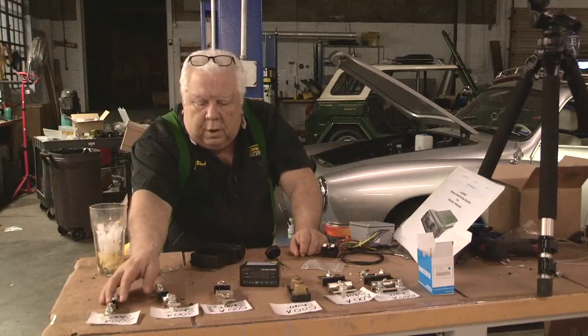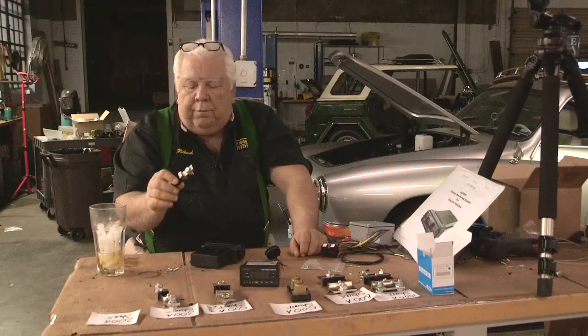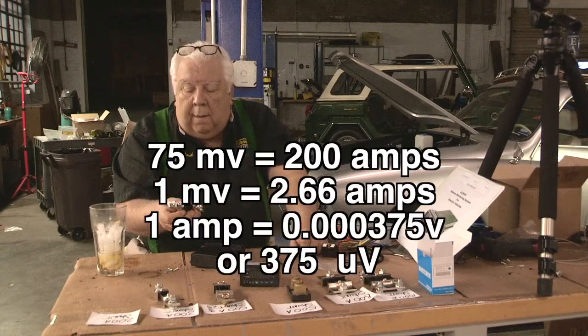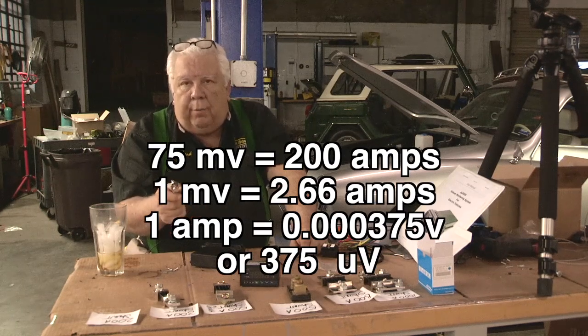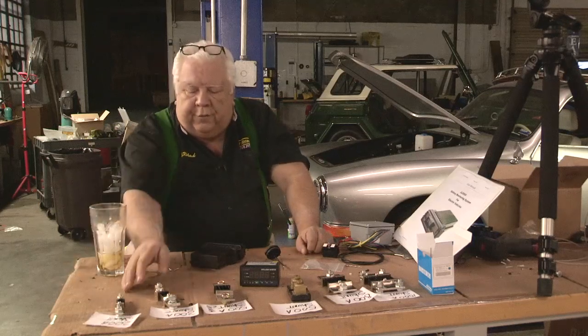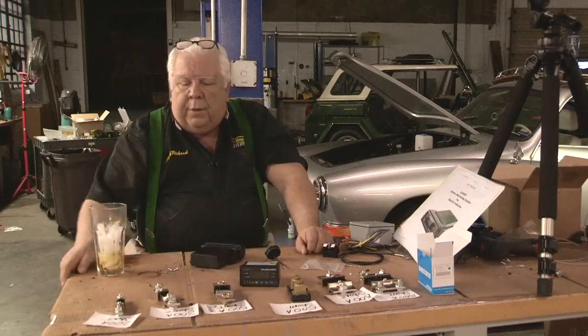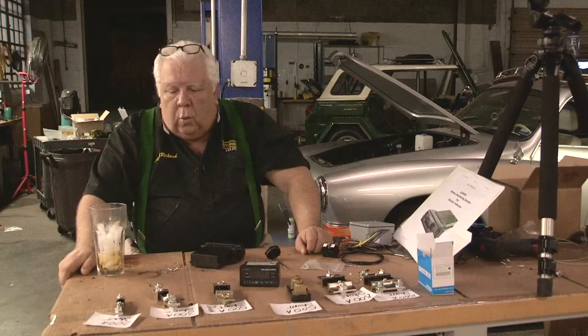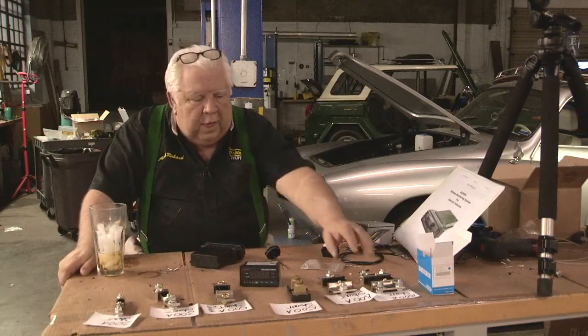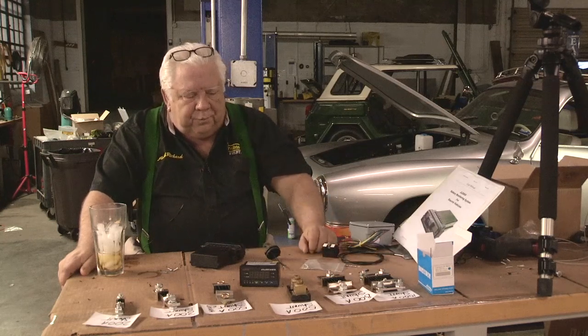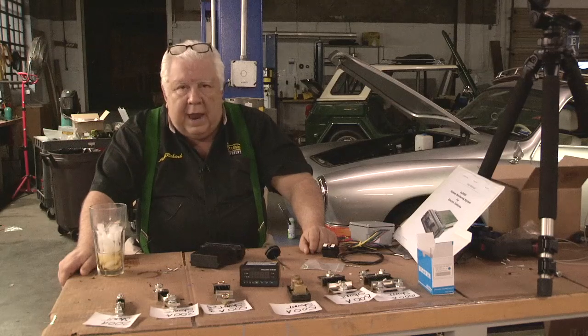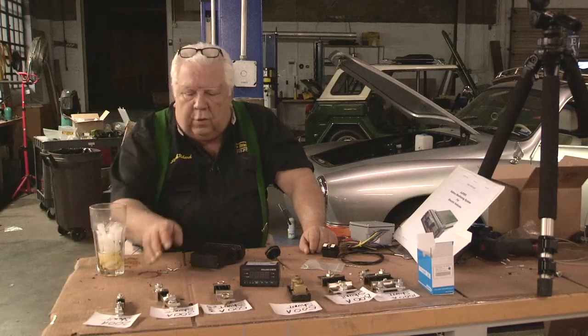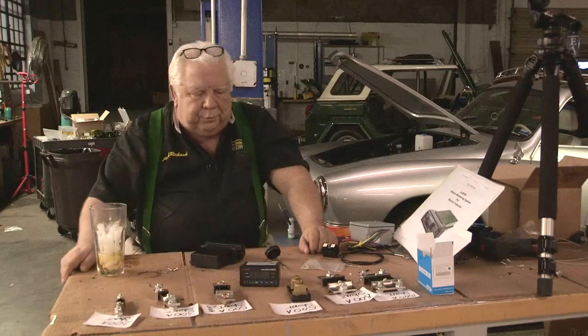Here's a 200 amp, 75 millivolt. Well, in that case, you're only reading about 3 amps per millivolt. The result is this is much more accurate because you have less current represented by more millivolts. 1,000 amps, 75 millivolts, you're talking about 1.33 amps per millivolt. Here we're talking about 3 amps per millivolt.